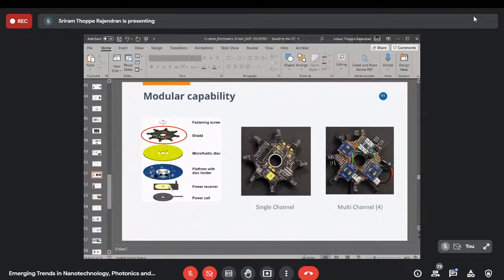So we don't have to make a new device entirely. We just have to swap the shield, put this shield in, and then keep measuring 4 channels at the same time. All the software is embedded in the bottom part, so no problem. This gives a superior capability. With a commercial instrument, you actually have to buy a separate instrument called a multi-channel potentiostat, which is really, really expensive. And that's another reason why we had to make a custom device, because a device like this just doesn't exist anywhere. We just made it ourselves.